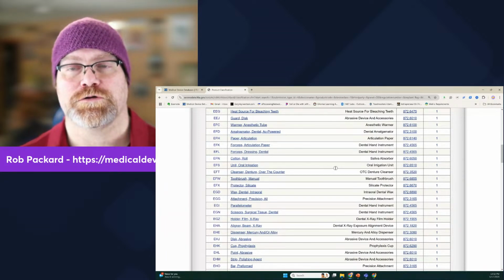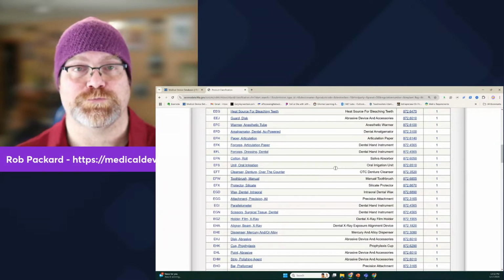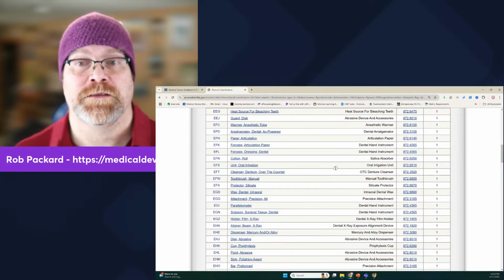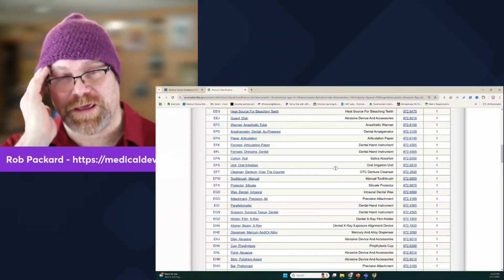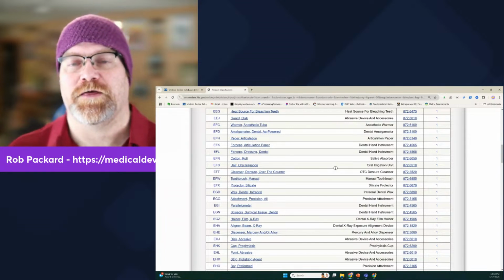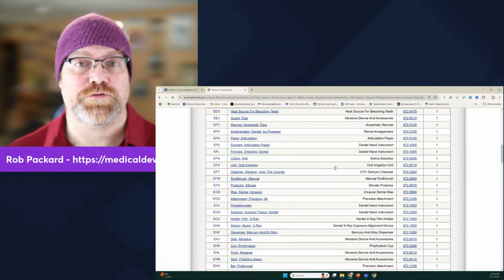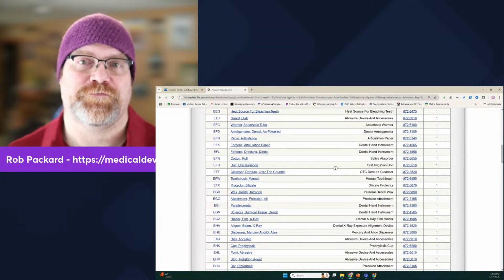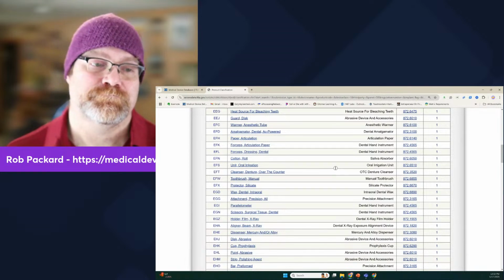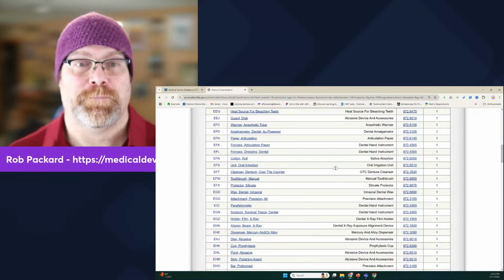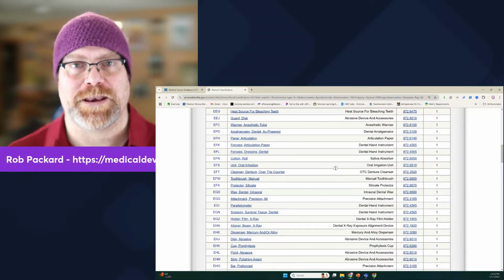So I was looking for product codes that are 510K required as the submission pathway, class 2, because I knew it would be something that was automated and had software and had some functionality that was sort of medium risk. So I knew it'd be class 2, I knew it'd be a 510K, and I knew it was in general hospital, and that's what I needed to find it. And I just had to go through the hundreds of items on the list until I found one that would work. And hundreds of items is searchable, even manually. Dozens, no brainer, really easy. But there are thousands of codes for the FDA, so you've got to search it in a systematic way and narrow down your list.